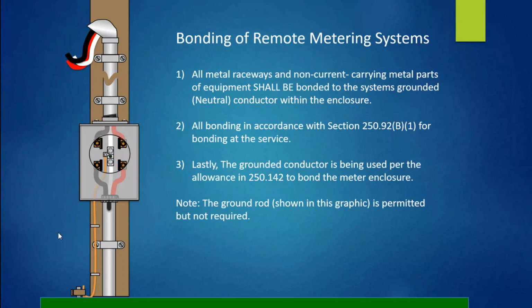Okay. Now, anybody out there would say, well, wait a minute, he's adding this grounding electrode system here, and you have a violation here. Well, like I said, if they used a ground rod, I would expect them to follow all the rules that are required for this. Now, they only have one ground rod, so silly me. They did a test on this, and they determined that it was 25 ohms or less, so it only needed one ground rod. Also, it's above the ground, so there is going to be a protective cone placed over this. Also, this ground rod actually is 10 feet long, so there is 8 feet in contact with the earth. I only had the little bit sticking out for illustration purposes only.